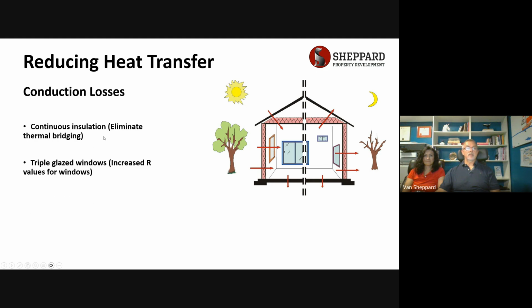Next one is triple glazed windows. And again, the R value of a conventional double glazed window is around R2-ish, and a well-built triple glazed window, the R value is about 5. Still not nearly as good as a wall, but 2.5 times better than a regular double glazed window. So it's a big deal. And in modern homes, the window area is significantly larger than it was in a home built, say, pre-1980. So the fact that the glazed area is increasing puts a premium on putting in good windows.